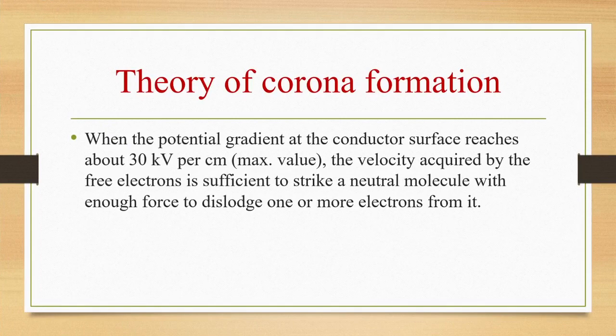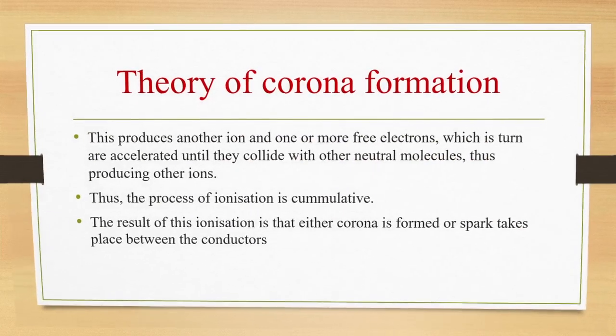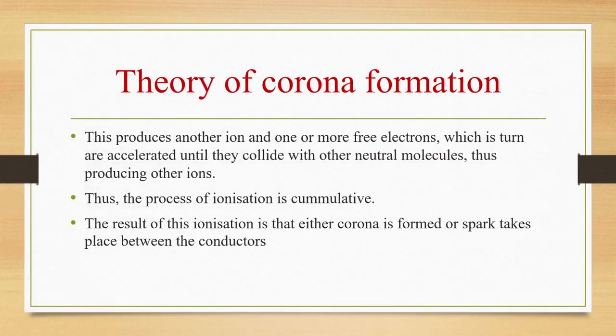So when the potential gradient at the conductor surface reaches about 30 kilovolt per centimeter, this is the maximum value for potential gradient, then the velocity acquired by the free electrons will be sufficient to strike a neutral molecule with enough force to dislodge one or more electrons from it. This will produce another ion and one or more free electrons, which in turn are accelerated until they collide with other neutral molecules. So they produce other ions. So this process of ionization is cumulative. It is a chain reaction. Okay. So the result of this ionization is that either the corona is formed or spark takes place between the conductors.